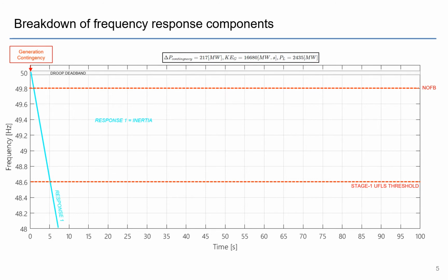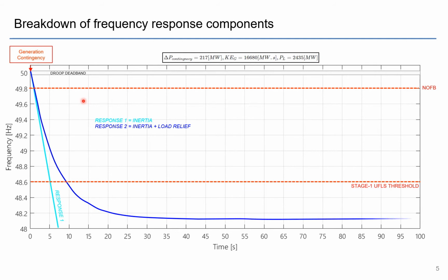Inertia is there to basically retard the fall in frequency. So if inertia was lower, it would just fall faster, basically. If we had inertia and load relief, so we had some load damping, this is what we would see. So load damping, we'll discuss this in more detail later, but load relief is basically the natural sensitivity of loads to frequency deviations. So there's quite a few loads like induction motors that actually just reduce their power output when frequency gets lower. So with load relief, you don't see it collapse all the way. I mean, it's pretty bad. It goes to 48.2 hertz, so you're already in the load shedding territory, but it does stabilize.